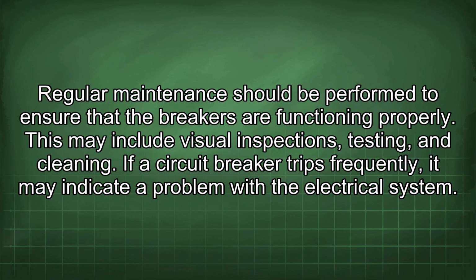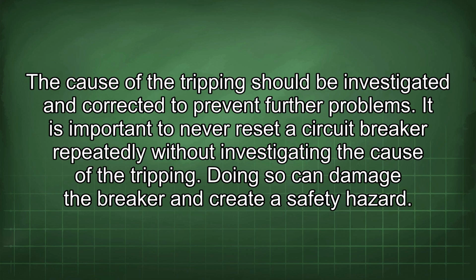If a circuit breaker trips frequently, it may indicate a problem with the electrical system. The cause of the tripping should be investigated and corrected to prevent further problems. It is important to never reset a circuit breaker repeatedly without investigating the cause of the tripping. Doing so can damage the breaker and create a safety hazard.